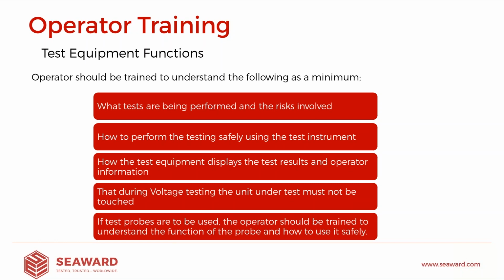They should also be trained to understand exactly how the test instrument is used, how to perform it safely, using the features within the instrument, and therefore understanding exactly what feedback the tester is giving the operator. So, for example, within the Seaward range of high-pot testers, we have different indicators for things such as pass or fail. We try to feed back exactly what the failure condition was, should a failure condition be met. But we also have other warning signs, so things such as red lights when there is high voltage present, that actually illuminates on the tester, separate from the beacon. So all of those things that the tester does and the way it displays results and any kind of operator information should be fully understood prior to being able to go out and perform the testing.